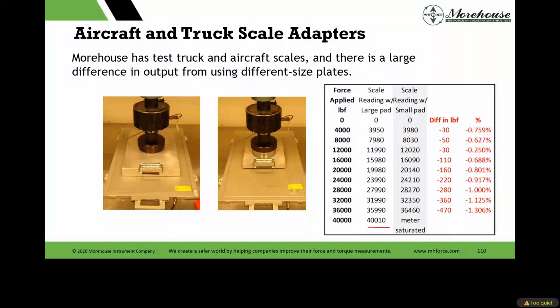No, the way this is gauged is probably not that linear. Though if I used a small pad on it, the difference was significant, 470 pounds at capacity and a 1.3% overall difference. If the tolerance is 1%, I'm not within the tolerance if I've switched my pads. So this is not a good scenario to be in as far as that goes.